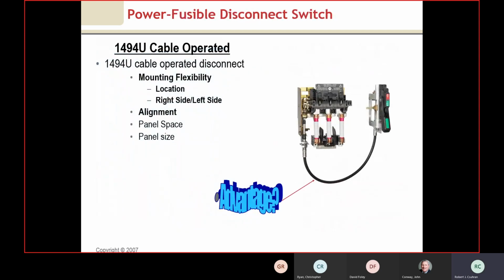The other option is the 1494 universal disconnect. With this design, we have flexibility in where the disconnect handle is mounted, because a cable now forms the connection between the two. You can still use a rod to turn it on and off, but the cable allows us to mount the handle on the right-hand or left-hand side, so alignment isn't a big issue.